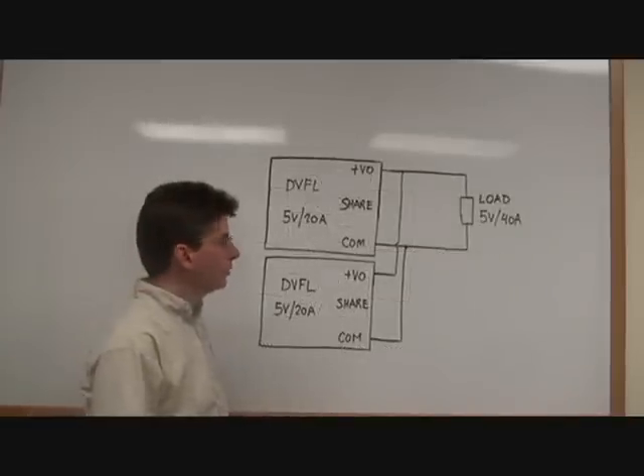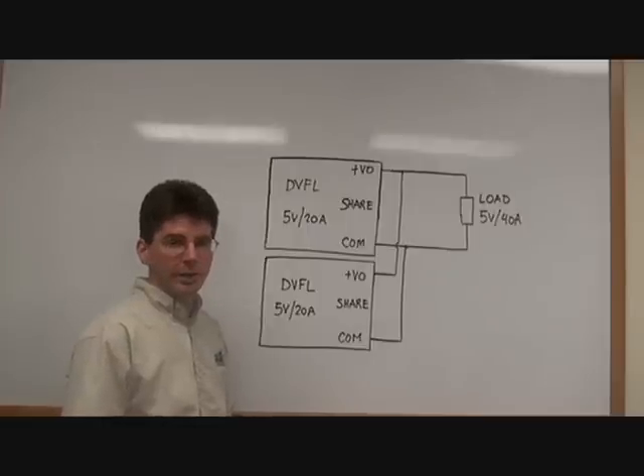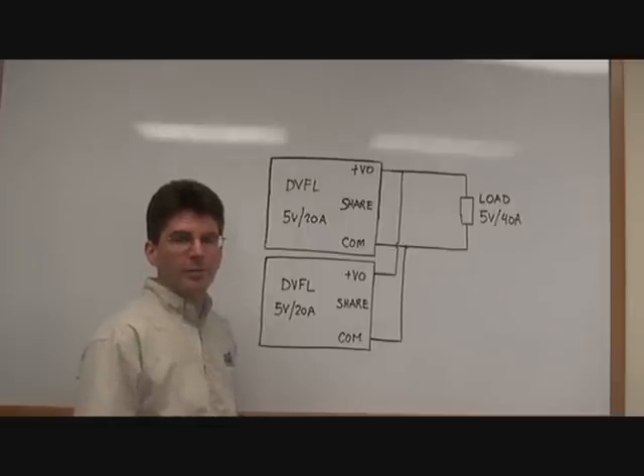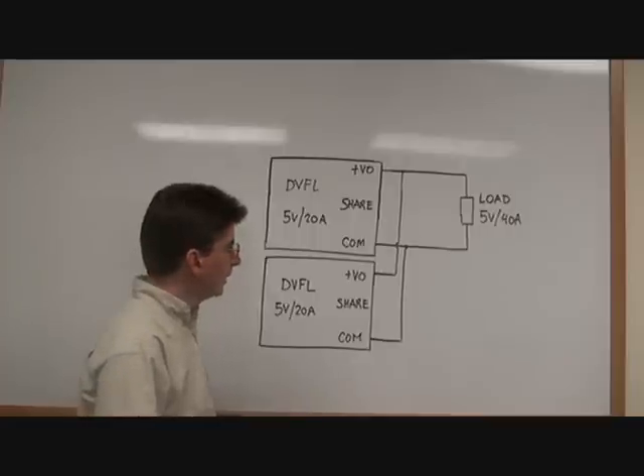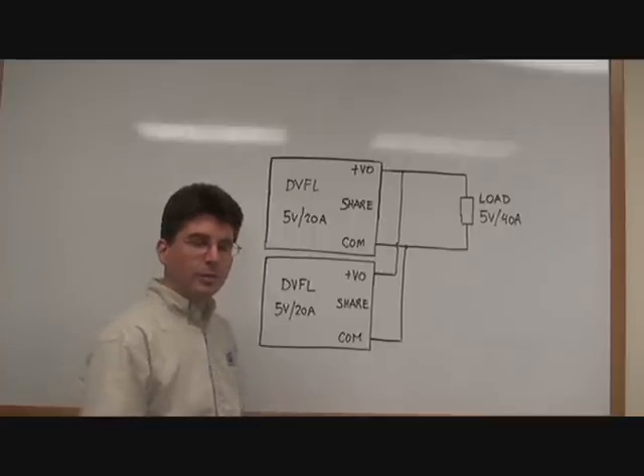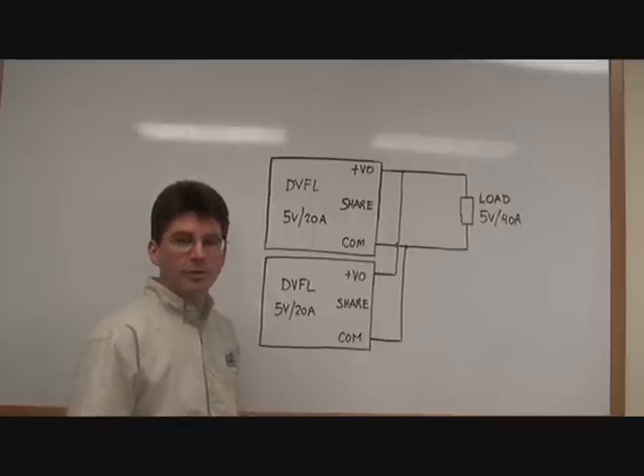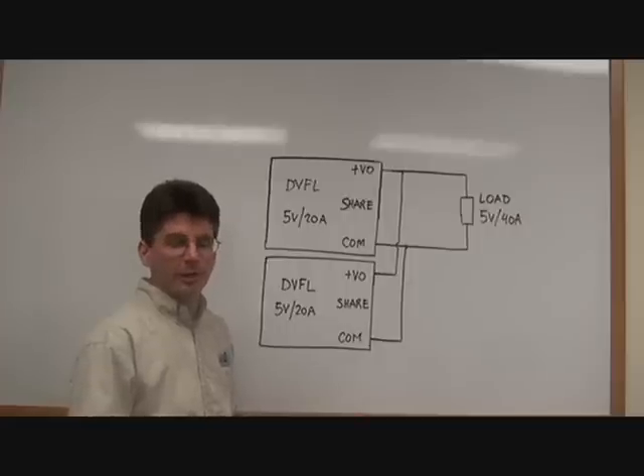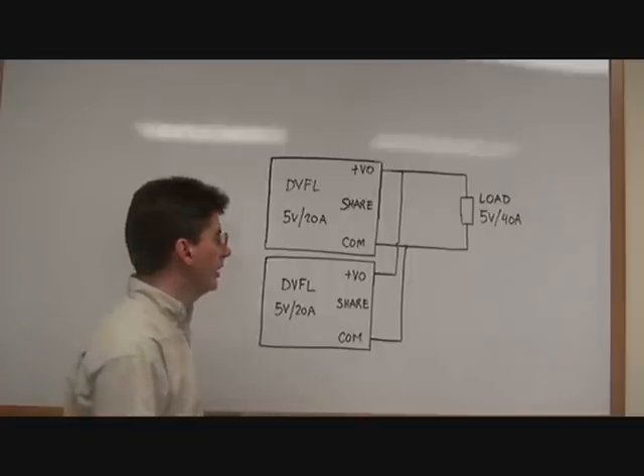This diagram shows two DVFL 2805S single output converters connected in parallel. Now, if left like this, one converter would take most of the load and the second would pick up the remaining load. So we connect the share line.